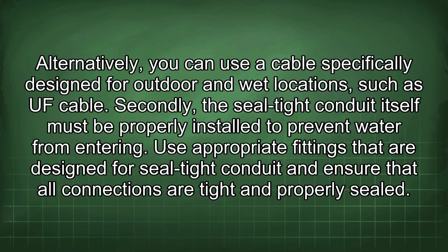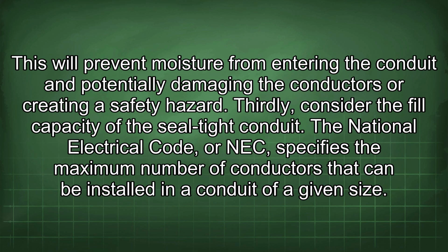Secondly, the seal-tight conduit itself must be properly installed to prevent water from entering. Use appropriate fittings that are designed for seal-tight conduit and ensure that all connections are tight and properly sealed. This will prevent moisture from entering the conduit and potentially damaging the conductors or creating a safety hazard.